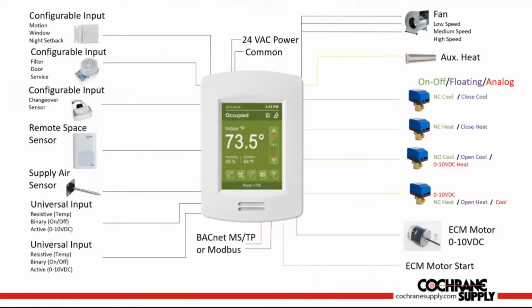Here's a look at all the options that are available on the 8350 room controller out of the box. Notice the controller has 7 inputs and 9 outputs that are used based upon the way in which the installer configures the room controller. Inputs can be configured for operations like window and door switches, dirty filter, or general service notification. A changeover sensor, either a contact closure or resistive temperature sensor, can be connected for 2-pipe system or zone control applications. A remote temperature sensor or supply air sensor, along with some open universal inputs, are available.